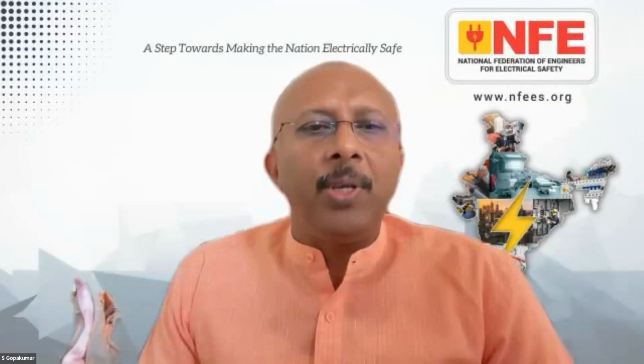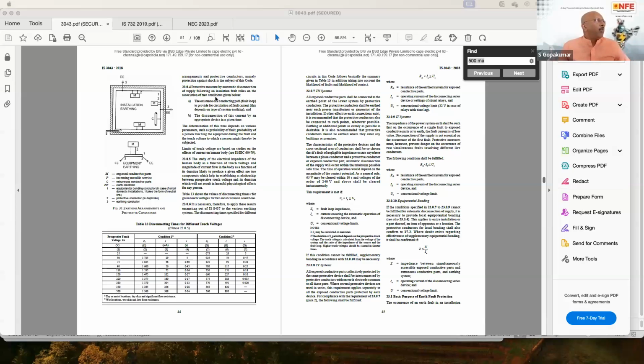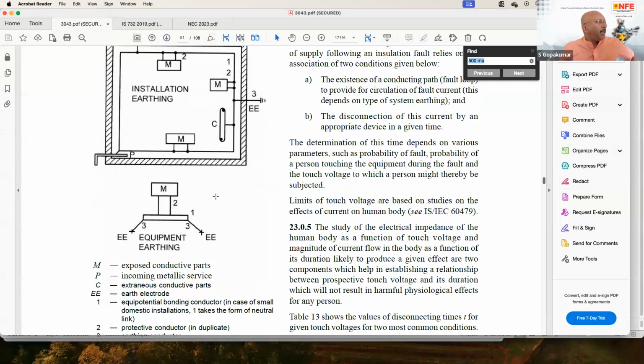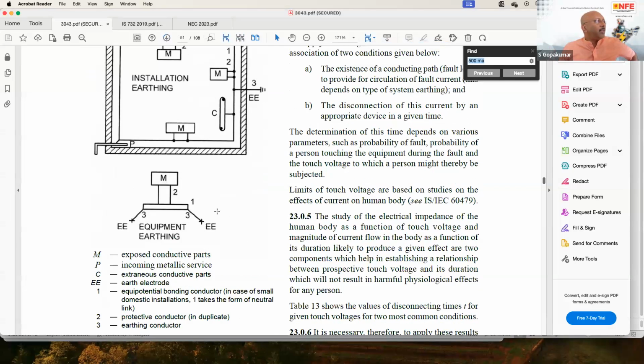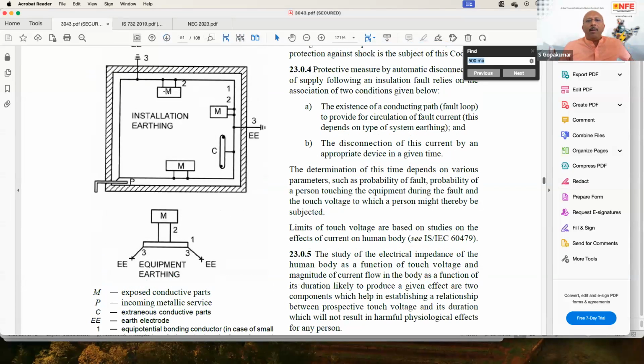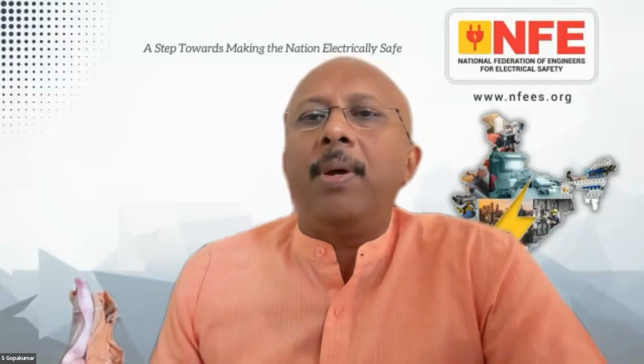Again, I show on the screen where it is written. You go to IS 3043. Here you can see Figure 31, earthing arrangement and protective conductors. Here you can see M. M stands for exposed conductive part, that means the metallic parts of electrical items. Then item number 1, the black colored ring, is the protective equipotential bonding, meaning the earth bus bar running along with the cables. So your equipment must be connected to the common earth bus bar with two connections. This is the explanation. Please download IS 3043, go to the clauses and have an idea about it.